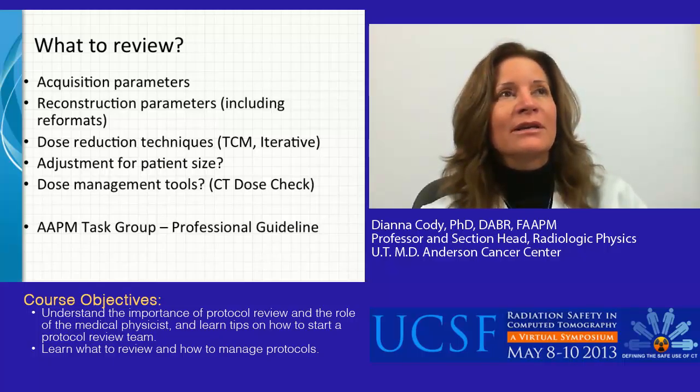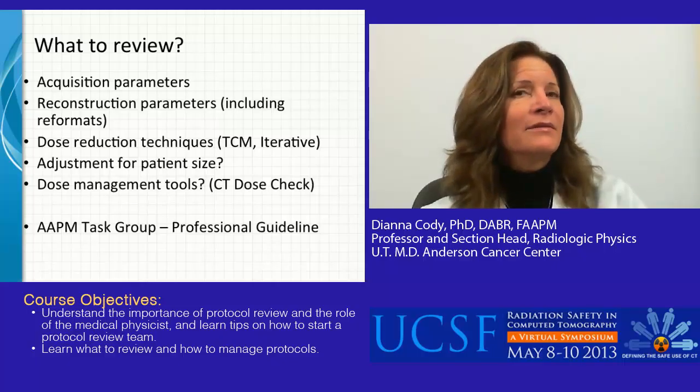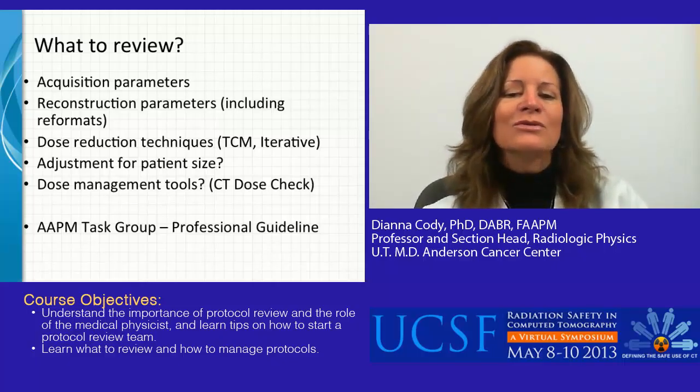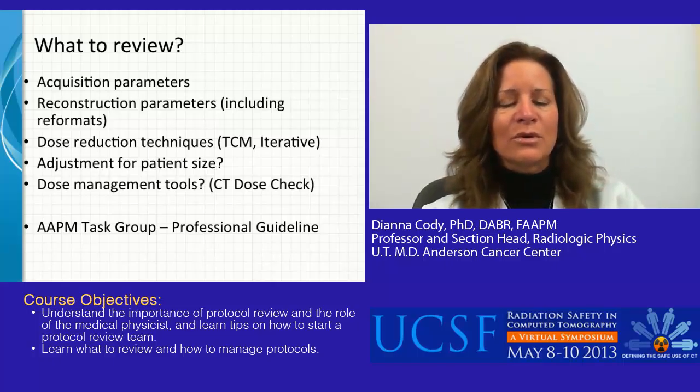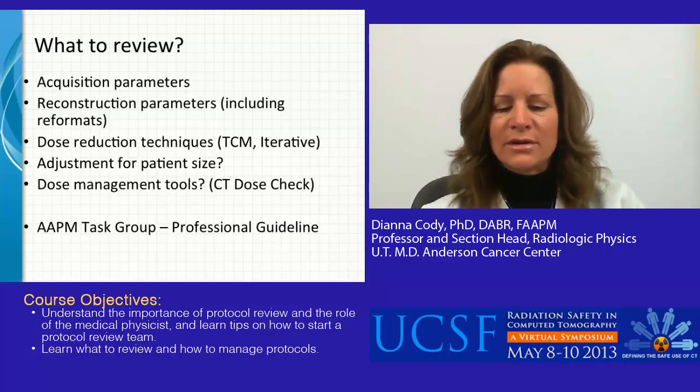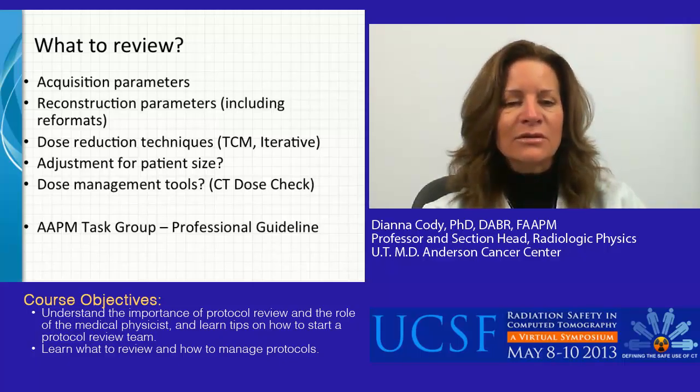If you're involved in the ACR CT Dose Index Registry program, this is another place to double check that everything is set up appropriately to send that structured dose report to the ACR. There is a professional guideline that should be publicly available in the next month or two from the AAPM that describes this review process. It may give you some additional help.